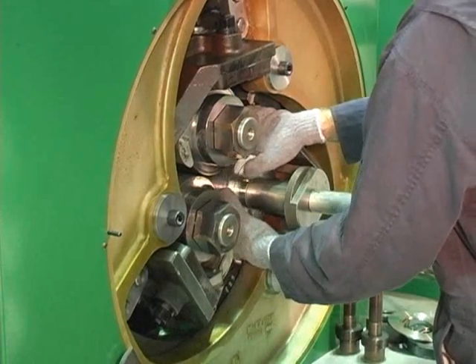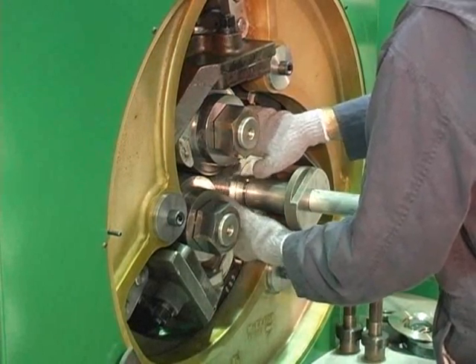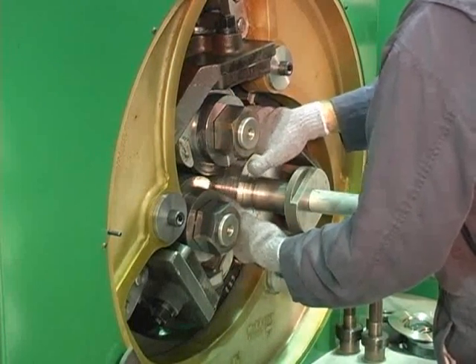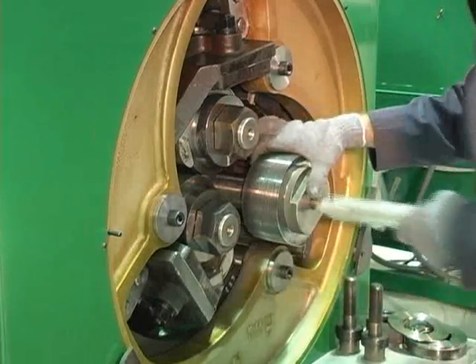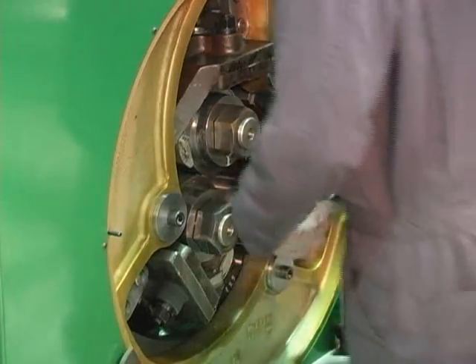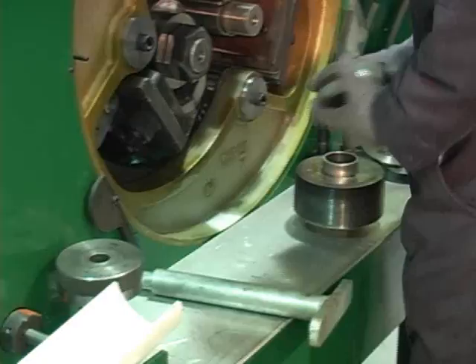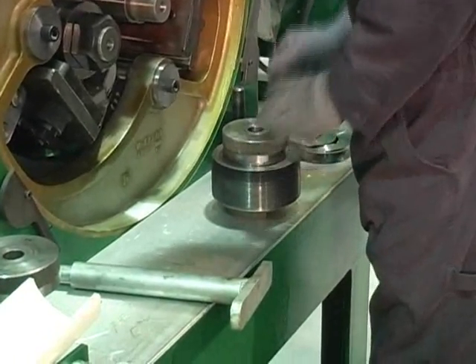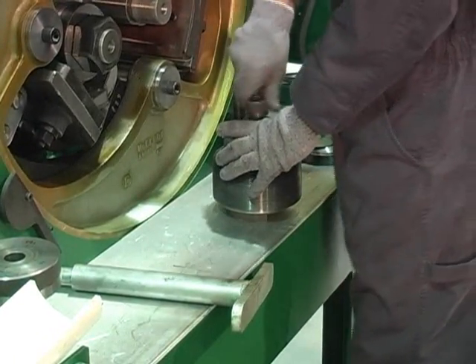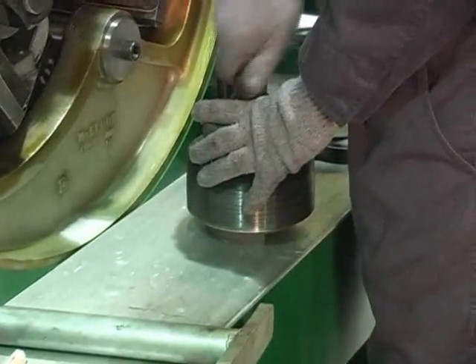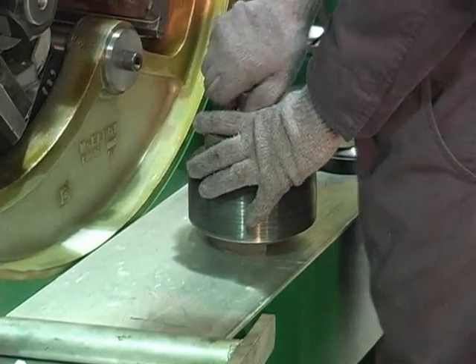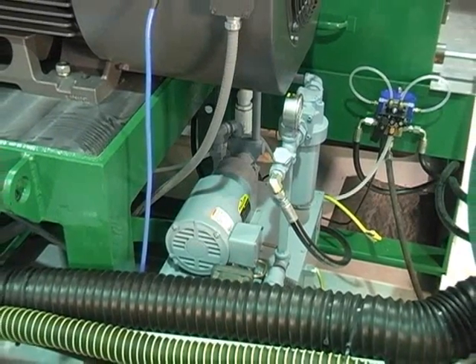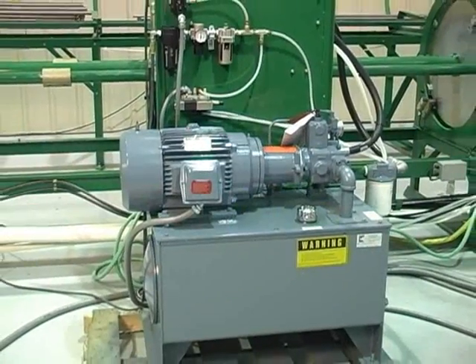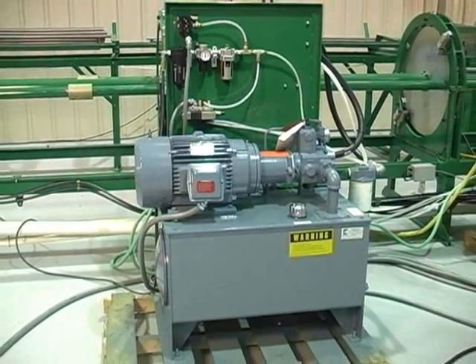Typical muff wall thickness of 0.172 inches on a 1-inch tube will produce 5/8 inch by 10 FPI at 0.67 pounds of aluminum per foot of tube. In addition, helix angle adjustment can be easily completed in less than 15 minutes. Because of the accessibility of the stack, all discs can be changed in less than 20 minutes. Located adjacent to the finning head is the oil rig unit, which provides oil to the disc arbors, and the hydraulic power unit, which provides the hydraulic reservoir for all machine functions.